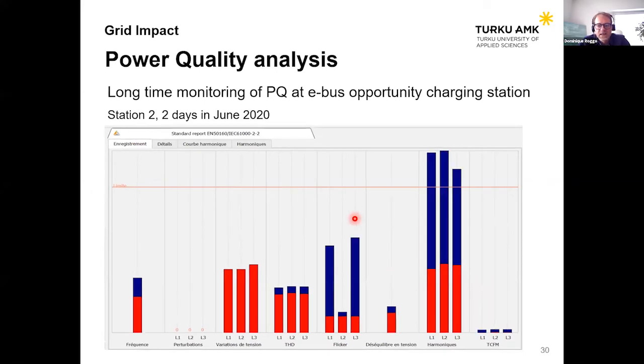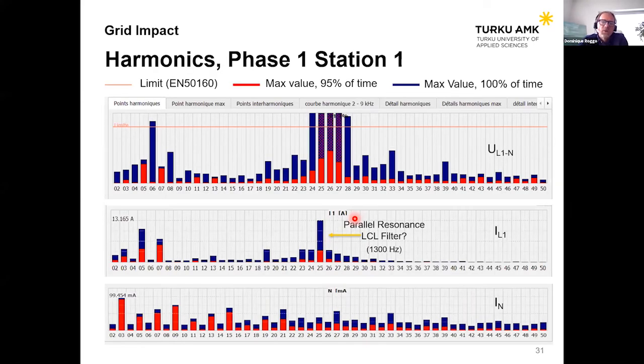So we wanted to analyze this a bit. Other charging stations show a similar situation, with problems only in the oscillations. We were able to analyze those oscillations at different frequencies, here you can see multiples of the fundamental. What we see very rapidly is some resonance in the order of 1,200 to 1,300 Hertz, which normally doesn't occur. The resonance is usually okay, but at times it clearly goes over the limits.